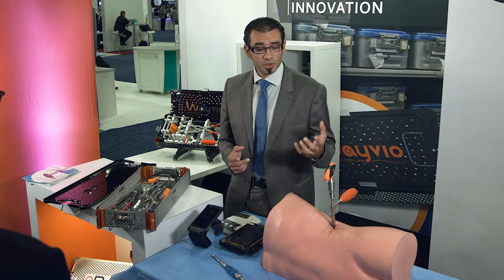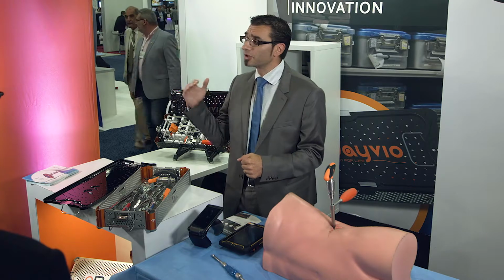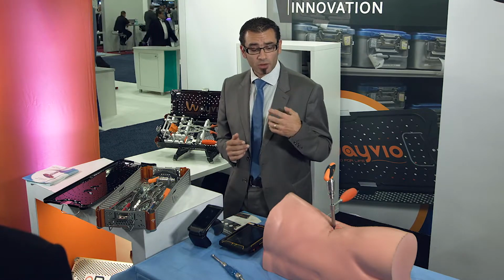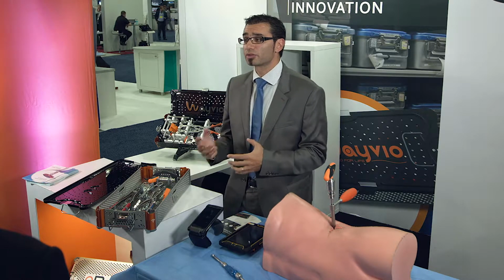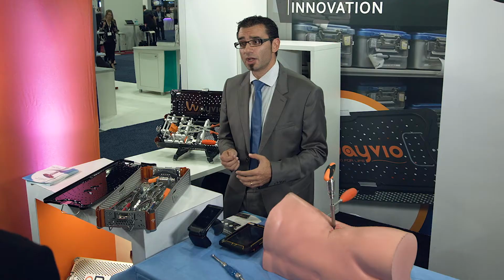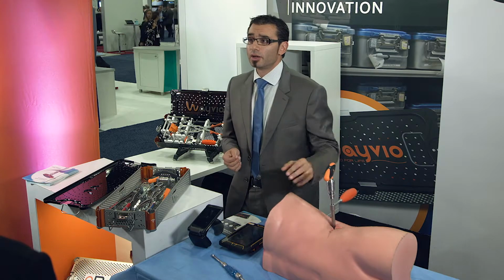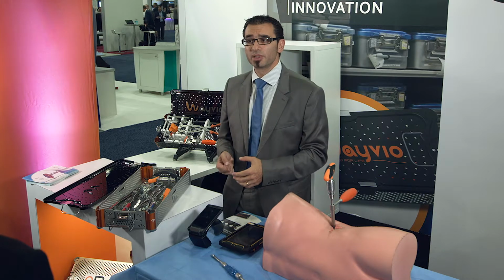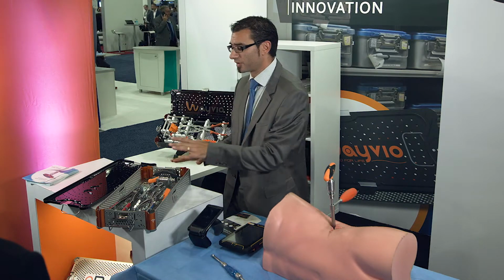That means we could have instruments that count the number of times they are impacted, and the level of impact on those instruments. We are also working on strain gauges to integrate on some instruments, giving you how many times a rod gripper or a rod cutter would be used, what was the level of distraction, and whether it was in conformance with what was required in the specification. So starting with this torque limiter, we have a wide array of possibilities to integrate Wayvio tomorrow in most of our instruments, whether they are identification instruments or just smart instruments.